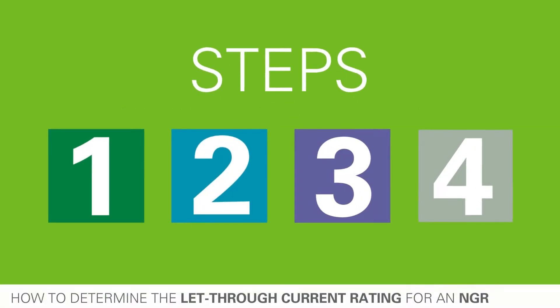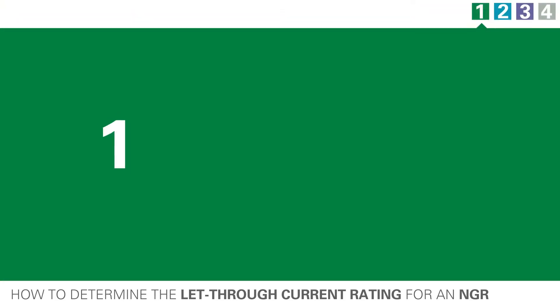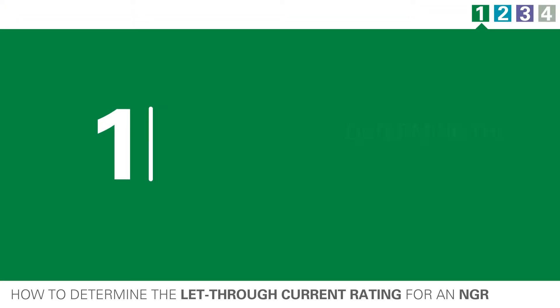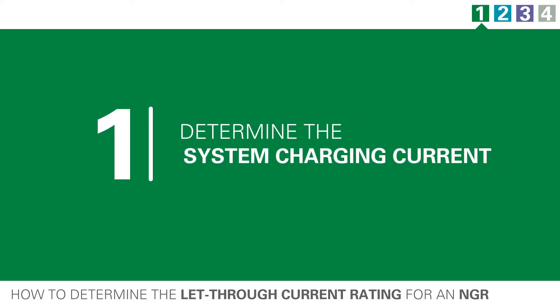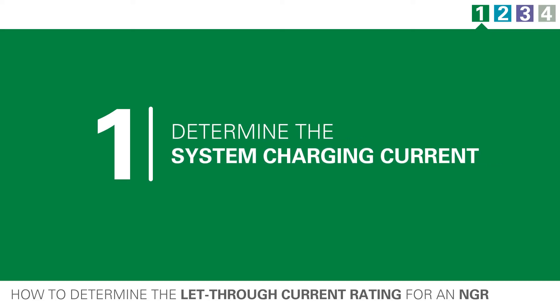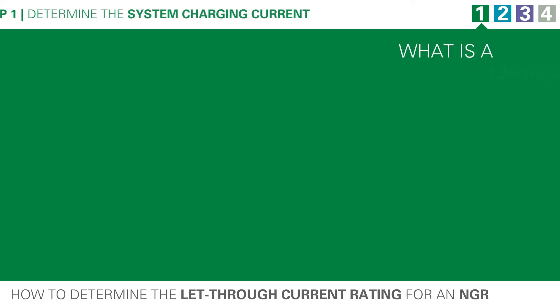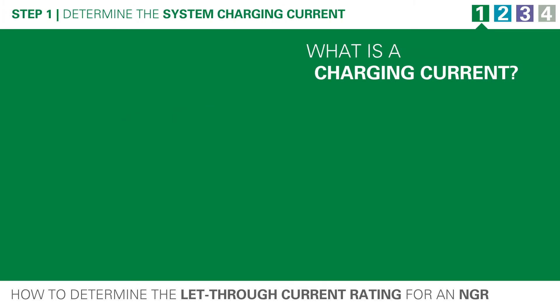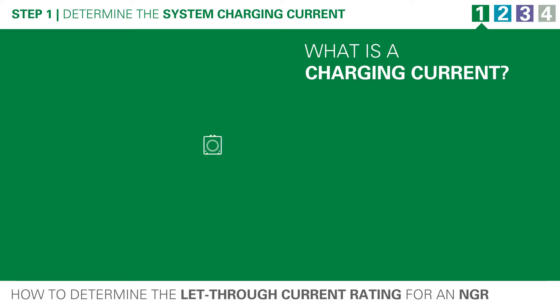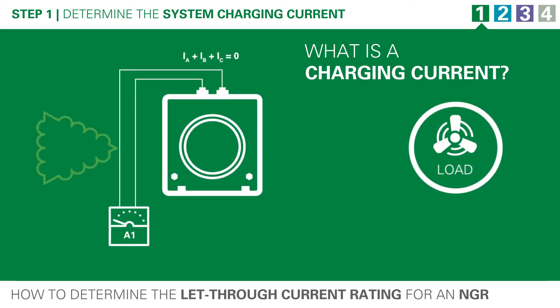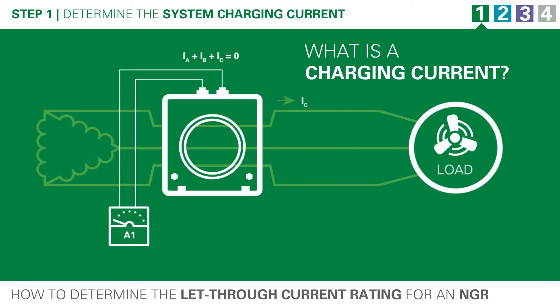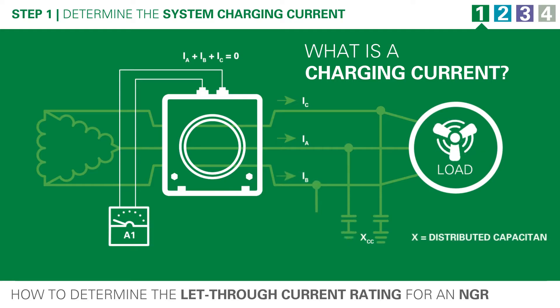We determine this in four steps. Step one: let's look at the system charging current. First, let's define charging current. An electrical system will have capacitance to ground, which is contributed to by cable length, surge arresters, motors, and other equipment.